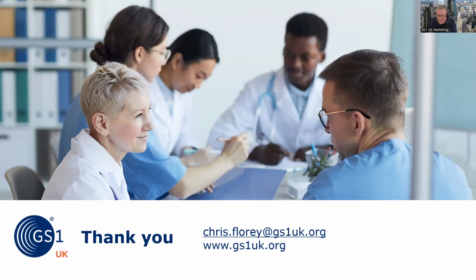I recently encountered an issue with a regulator regarding our UDI formatting. According to GS1 standards, do you think it is required that the full UDI be presented on a single line, or is it acceptable for the application identifier to be separate from the corresponding number? We have placed symbols next to numbers with the application identifier positioned below the symbol. Okay, great. Thank you, Stephanie. If you can email me with images of those, we can then have an offline discussion about that.